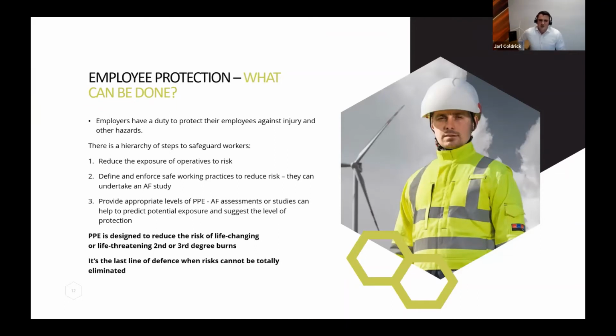So just summarizing this section, employee protection: what can be done? The employers have the duty to protect their employees against risk of injury and other hazards. And there's a hierarchy to safeguarding your workforce. Number one is reducing the exposure of operatives to the risk. Number two is to define and enforce safe working practices to reduce the risk. If you've got a risk of Arc Flash, you can do that by undertaking an Arc Flash study. That can be done internally by one of your senior electrical engineers, or externally by an electrical consultant. And number three, whilst it is the last line of defense, is the PPE, but it's still a defense because often the risk cannot be totally eliminated.